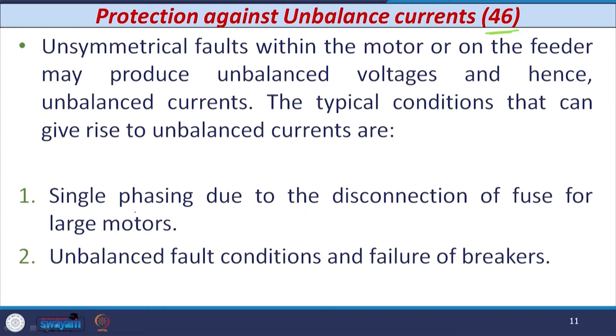The typical conditions that can give rise to unbalanced currents are: first, single phasing — because of disconnection of a fuse or disconnection of large motors; and second, unbalanced fault conditions and failure of circuit breakers. Because of either of these two reasons, unbalanced currents may be produced and the motor has to be protected against such unbalanced currents.